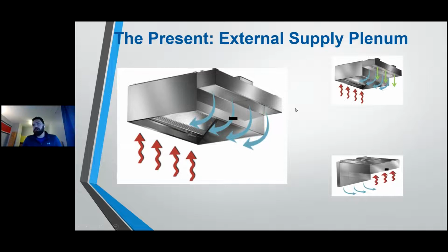You're going to have what's called a perforated supply plenum, and everybody has a different nomenclature for it, but a perforated supply plenum. This is where you're going to bring in that heated makeup air. So let's say you made the decision, on your dedicated makeup air fan, to only do heated makeup air. You're not even going to do cooling on that makeup air. You're just going to do heated makeup air. You're going to bring that air in. We're trying to pressurize this space, but that air is only heated. So in the summer or in those transition months, the air is really coming in untempered.